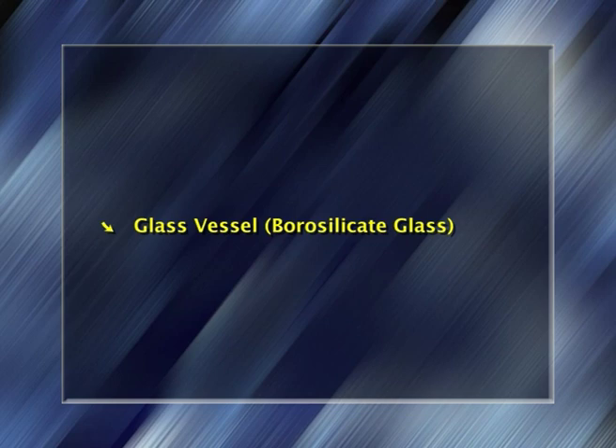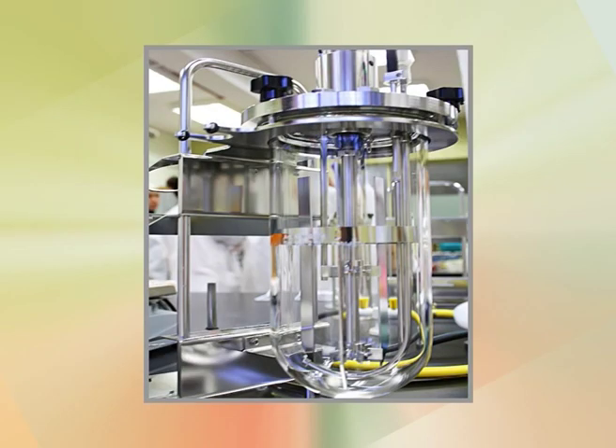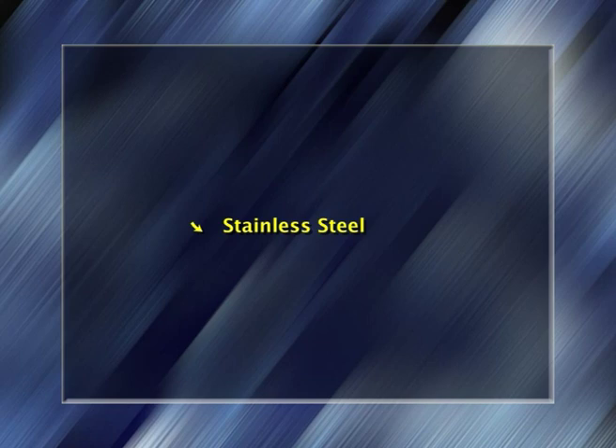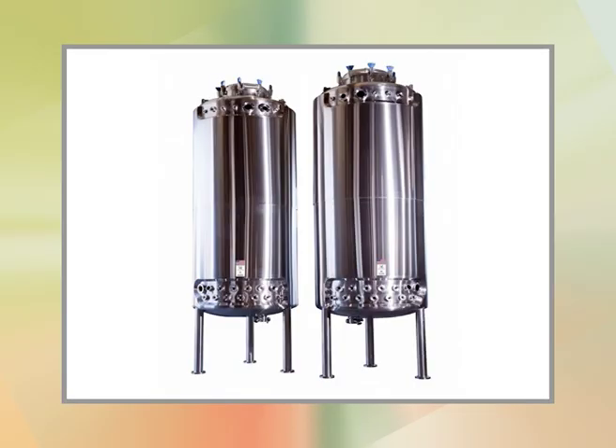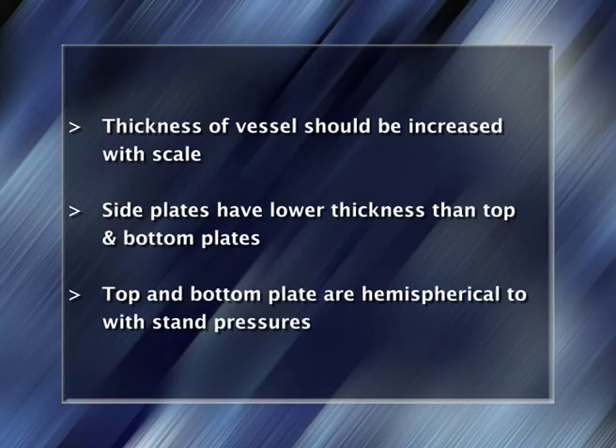For glass vessels, borosilicate glass is used. Type 1: a glass vessel with round or flat bottom with top plate — it can be sterilized by autoclaving and the largest diameter is 60 cm. Type 2: a glass vessel with flat bottom and top and bottom stainless steel plates — this type is used in in-situ sterilization processes and the largest diameter is 30 cm. For stainless steel, the thickness of the vessel should be increased with scale; side plates have lower thickness than top and bottom plates; and top and bottom plates are hemispherical to withstand pressures.